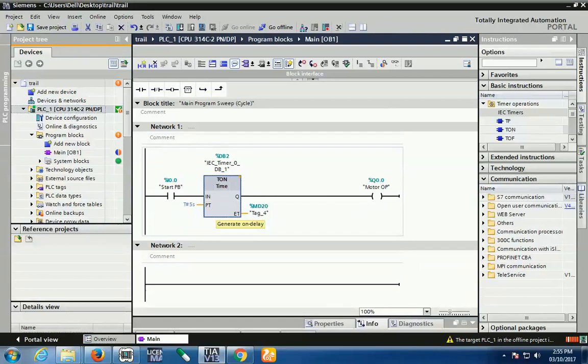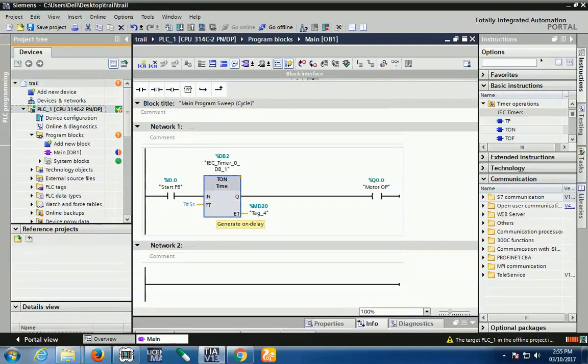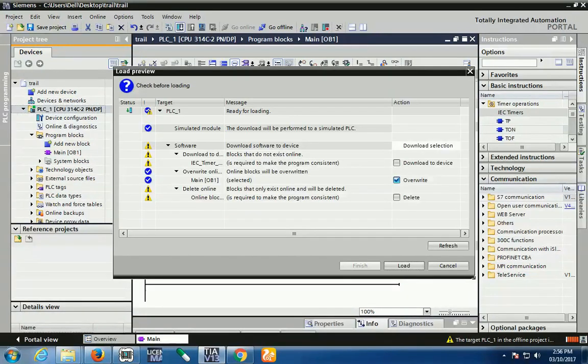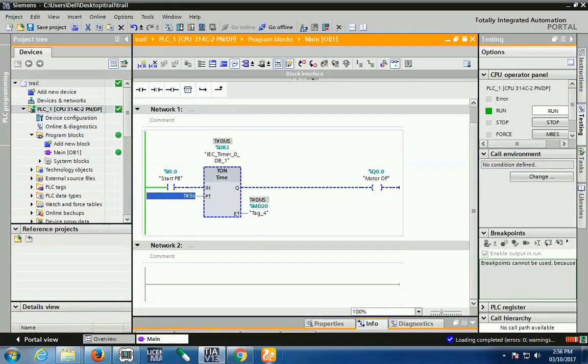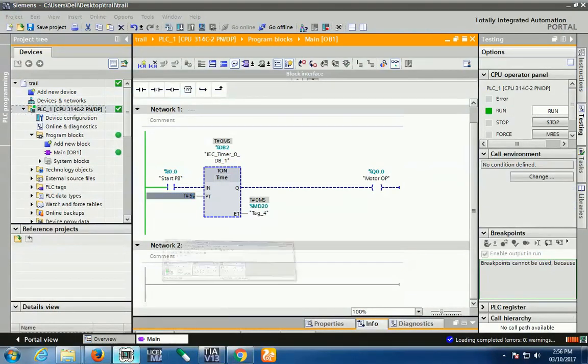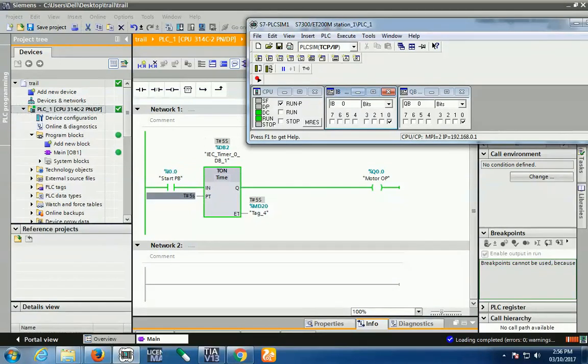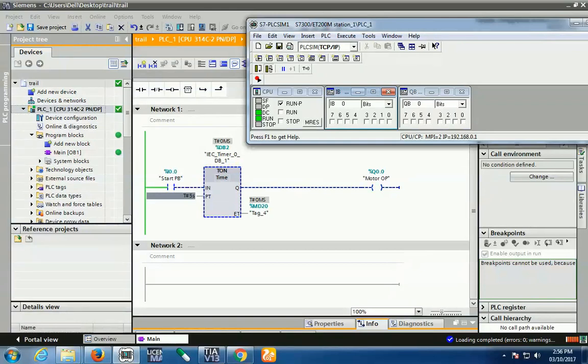Based on the performance of TON, if I press the input, my timer is activated. TON is an on-delay timer, meaning my output should turn on after 5 seconds because I set the preset time to 5 seconds. Now I'll download and check. When it's online, if I press, your timer time starts now, and you'll see your output should turn on in 5 seconds. If I release the start button, I cut off the enable command and your output turns off.